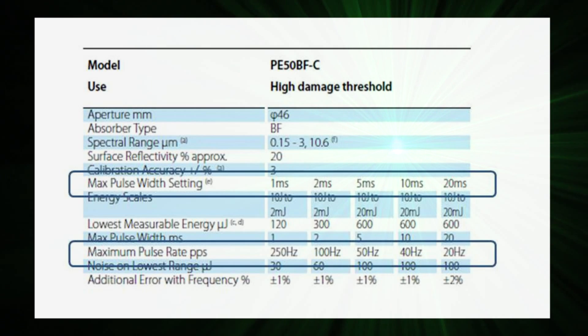The Pyro-C sensor's circuitry allows them to measure long pulses as well as short pulses and work at a high duty cycle, where the pulse width is as much as 40% of the total cycle time.